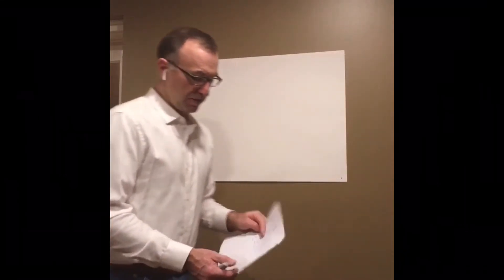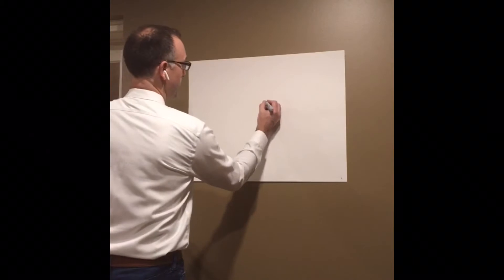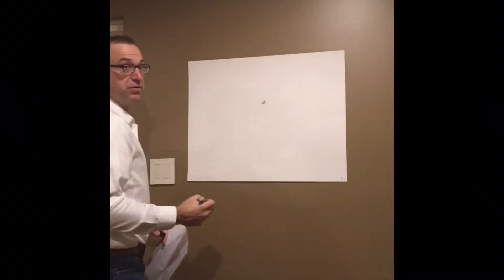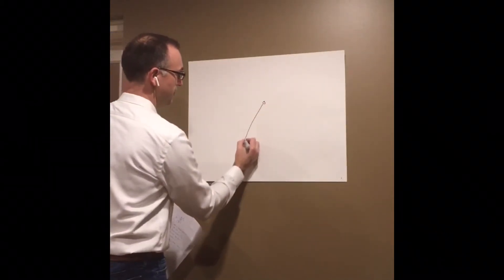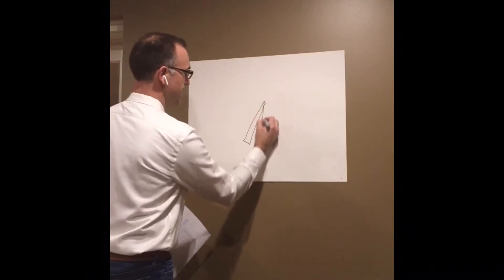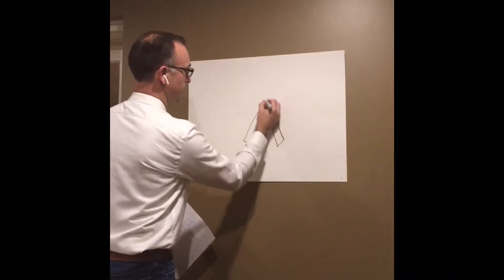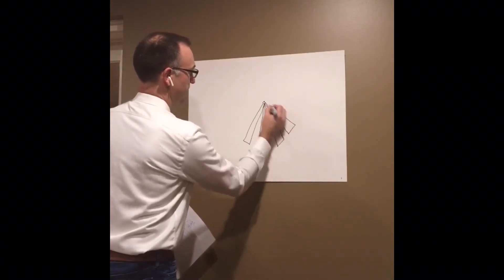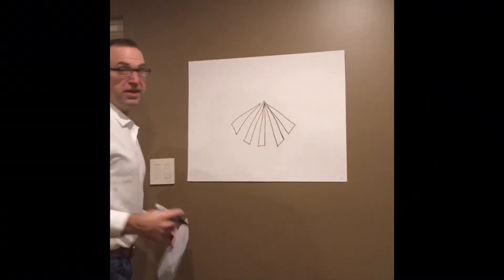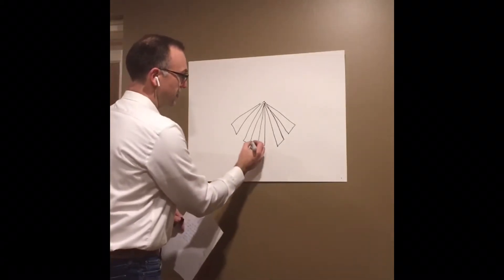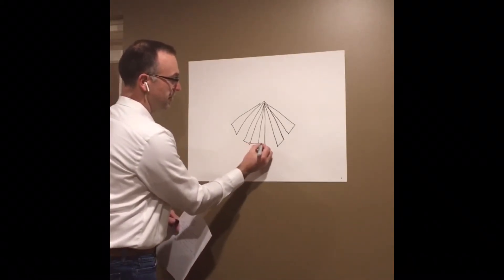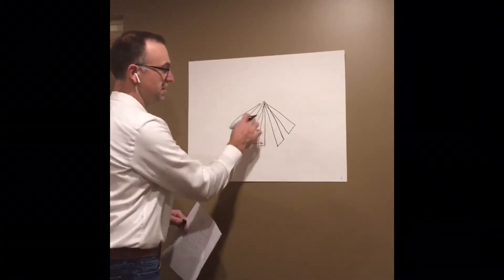And if I make a little sketch here, if we take that sensor and we put it in the center of our room, what it has is these little pie-shaped sensing zones that come out of the sensor. One more over here. And the way that it senses motion is actually when you move perpendicular to these sensing zones.